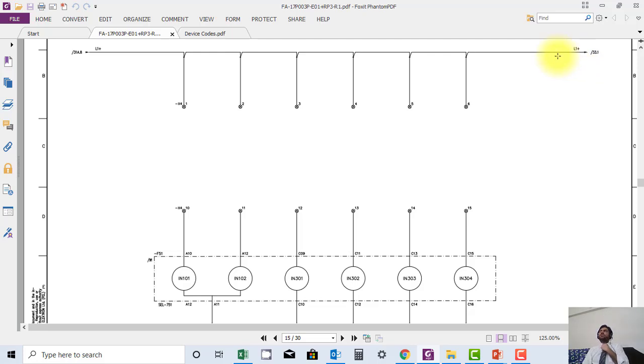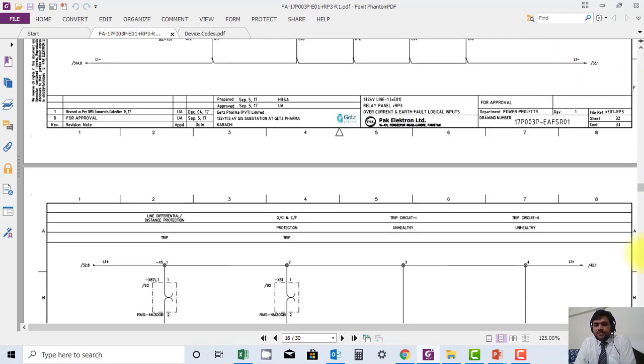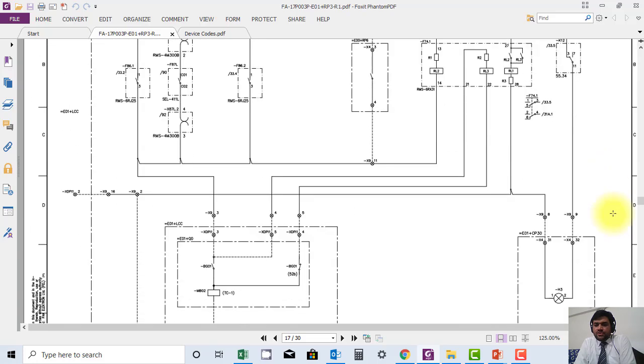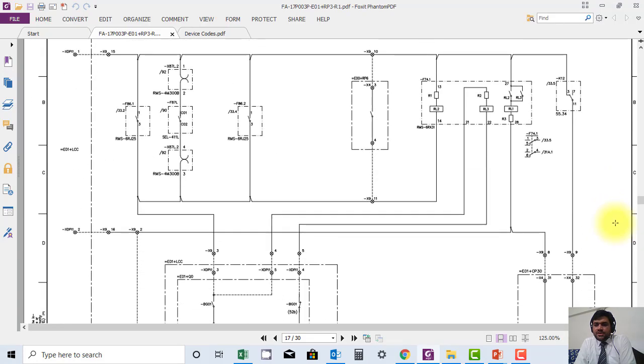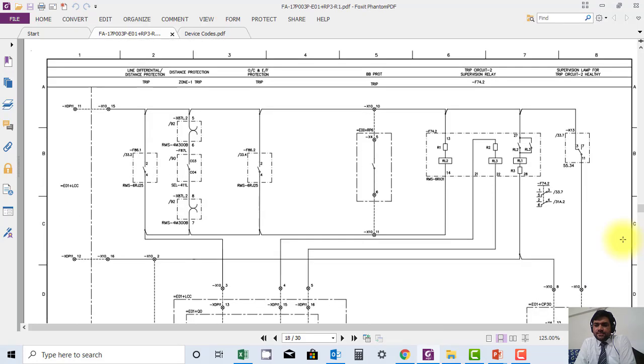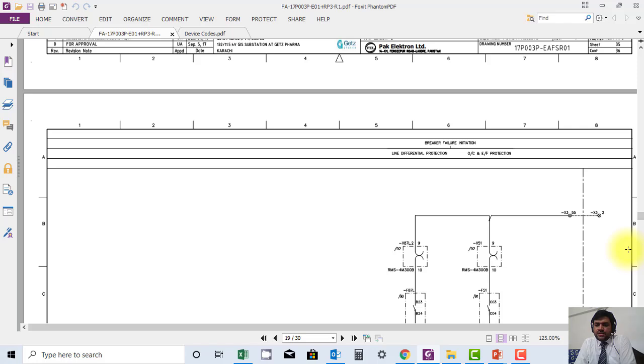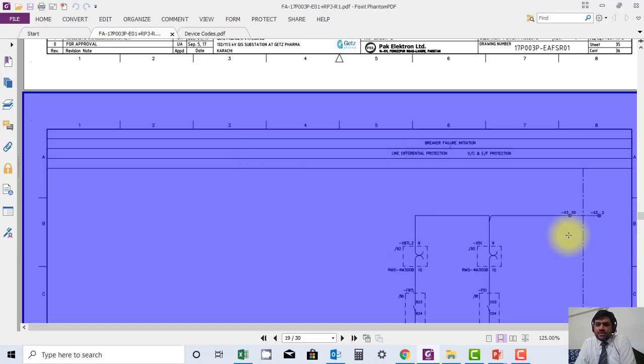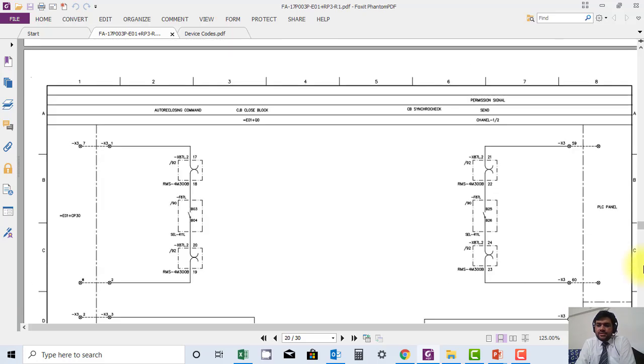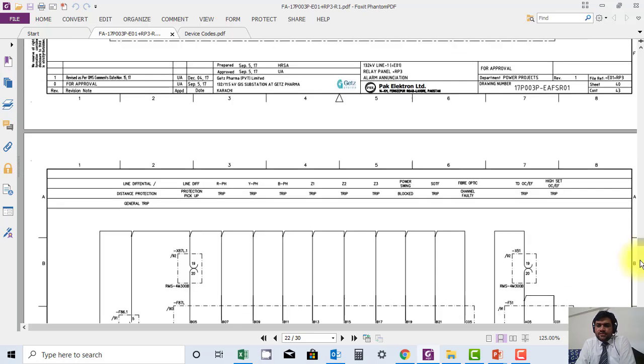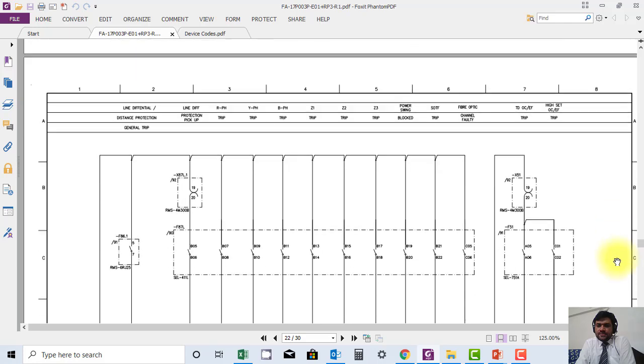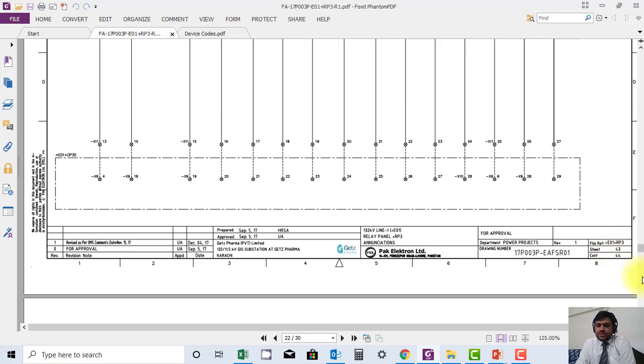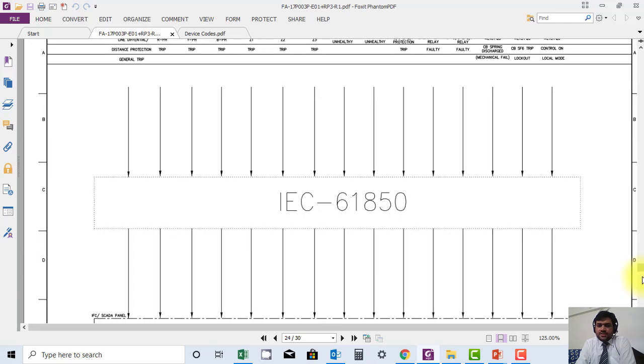How will the professional or maintenance engineer know that it needs attention? You have to install at the end of the loop a DC supervision relay. What this relay will be doing is simply: if the supply fails, this relay will give an indication to the protection panel that supply has failed.